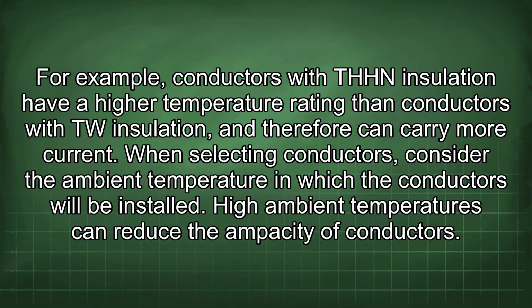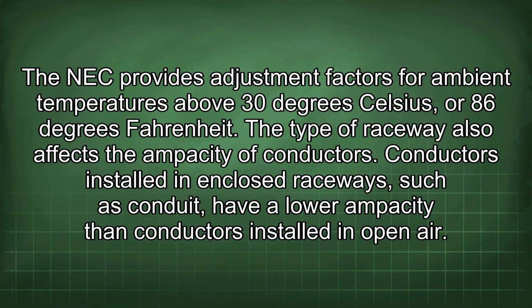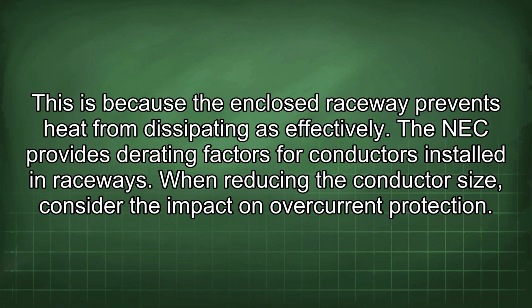High ambient temperatures can reduce the ampacity of conductors. The NEC provides adjustment factors for ambient temperatures above 30 degrees Celsius or 86 degrees Fahrenheit. The type of raceway also affects the ampacity of conductors. Conductors installed in enclosed raceways, such as conduit, have a lower ampacity than conductors installed in open air. This is because the enclosed raceway prevents heat from dissipating as effectively. The NEC provides derating factors for conductors installed in raceways.